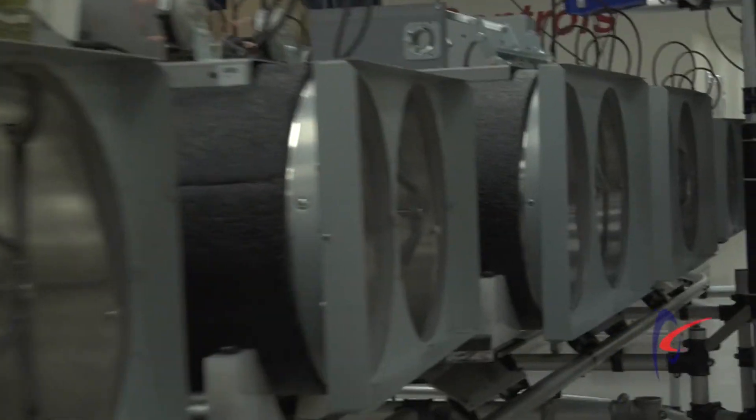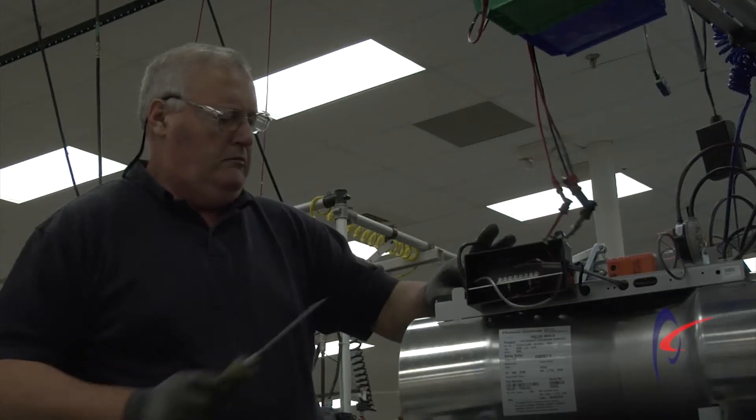Valve characterization is the process that Phoenix Controls uses to verify every single valve that's built throughout the manufacturing process.